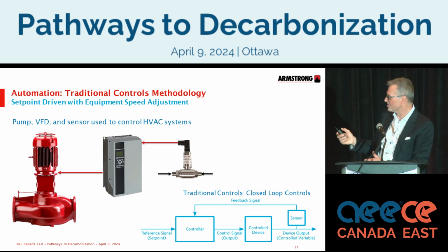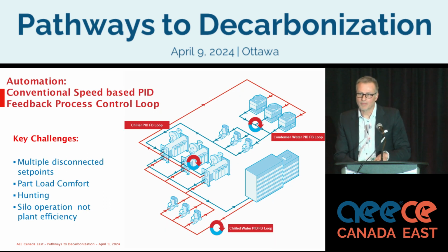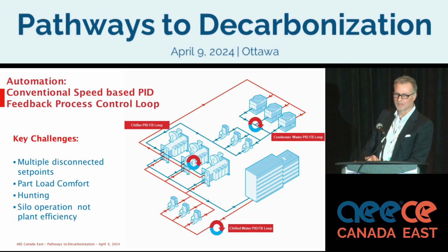Now, if you look at the entire chilled water plant, it's multiple disconnected set points. You have the building load. The chilled water pumps respond to the building load. The chillers then respond to the demand from the chilled water pumps, and then the condenser loop responds to the demand for the chillers. They're multiple disconnected set points. We're trying to achieve part load comfort, but we're always hunting to get back to a stable state. And so it's a silo operation and does not take into account plant efficiency.